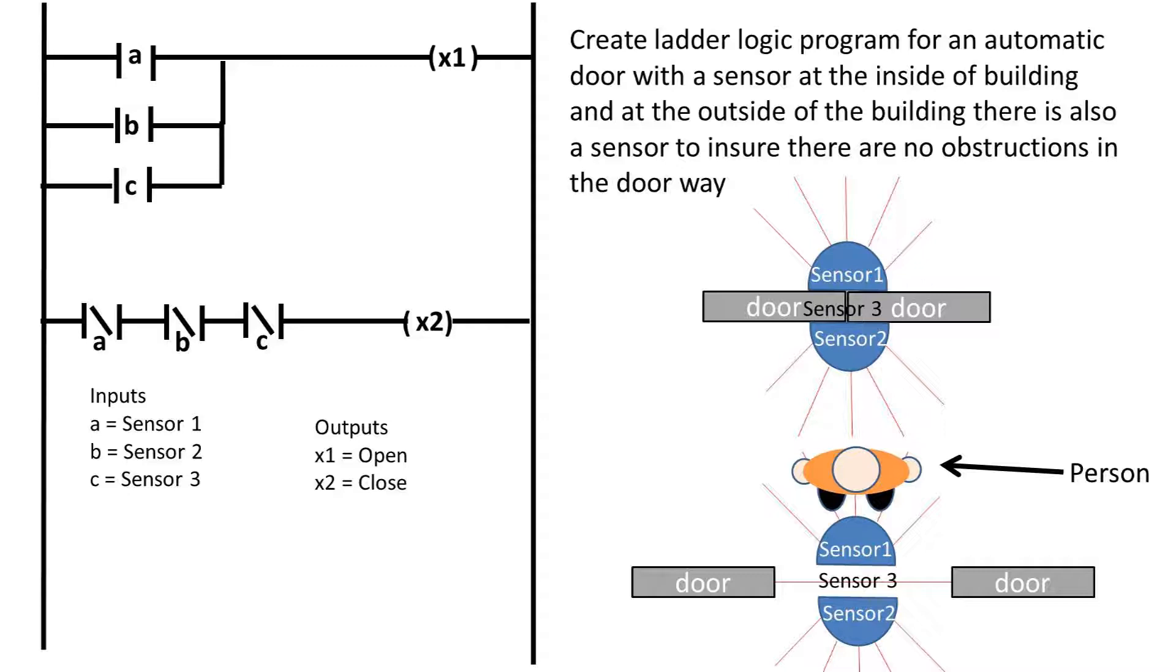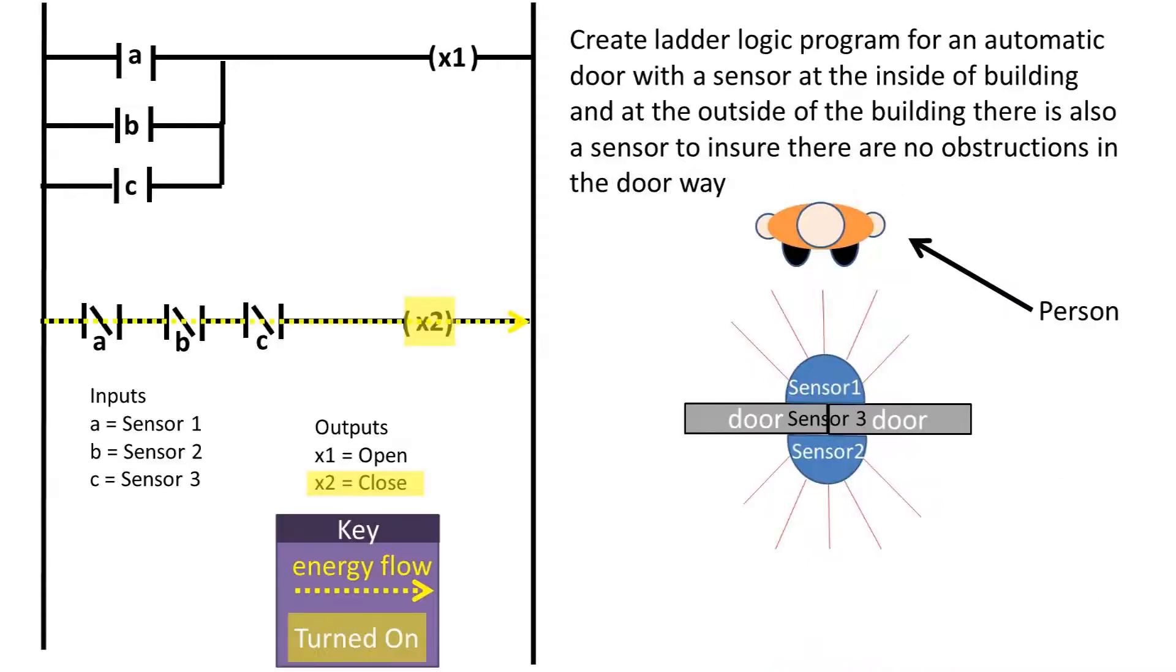This is stating that if there is no person or object in the way of the sensors, then the connection will be made to the coil to close the door. If any of the sensors report a true or on signal, then the normally closed contact opens and breaks the circuit, and the coil is not powered on.